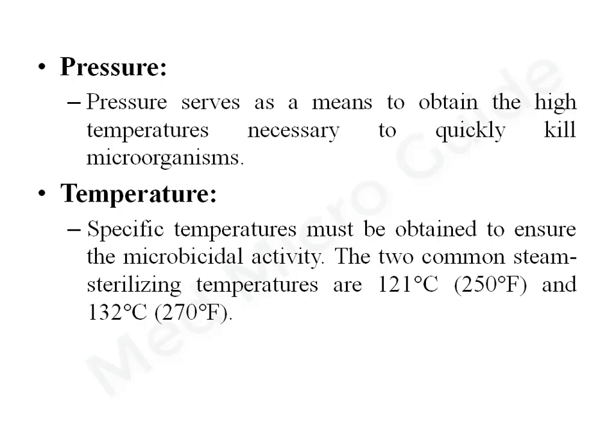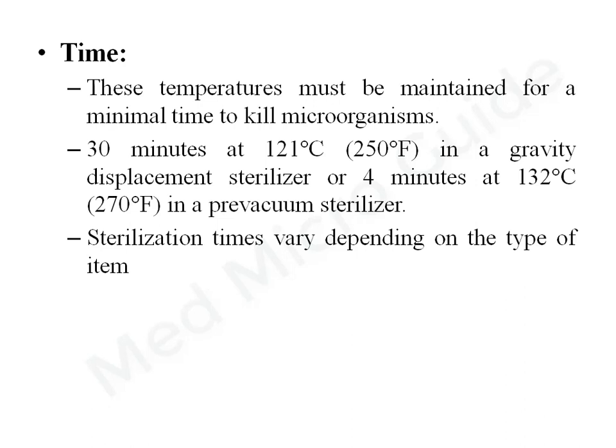There are certain standard pressures required to reach specific temperatures. A desired temperature must be obtained to ensure the microbicidal activity of sterilization. The two common steam sterilization temperatures are 121 degrees Celsius and 132 degrees Celsius. A minimum holding time of 30 minutes at 121 degrees Celsius and 15 pounds is required in a gravity displacement sterilizer, or 4 minutes at 132 degrees Celsius at 30 pounds of pressure in a pre-vacuum sterilizer.